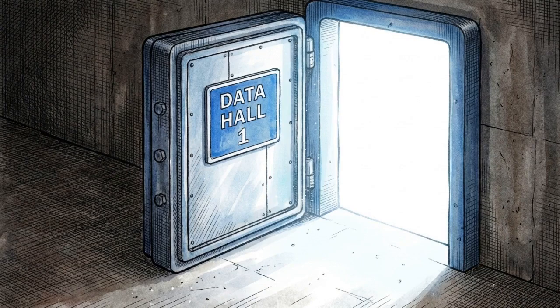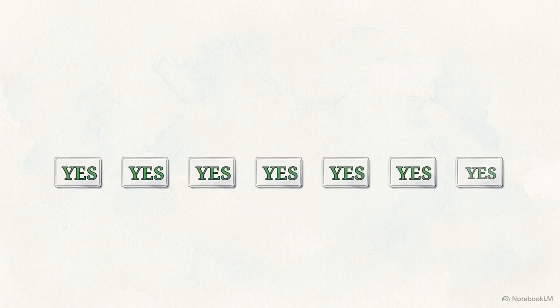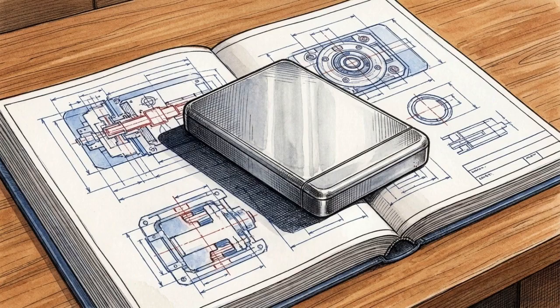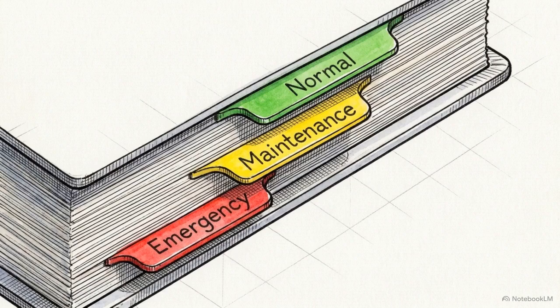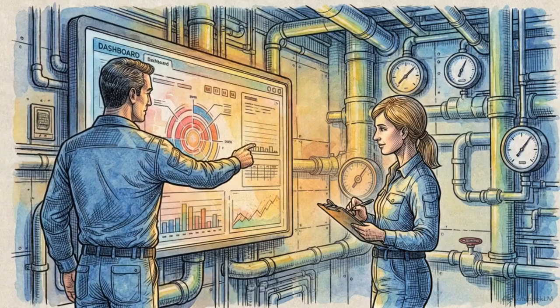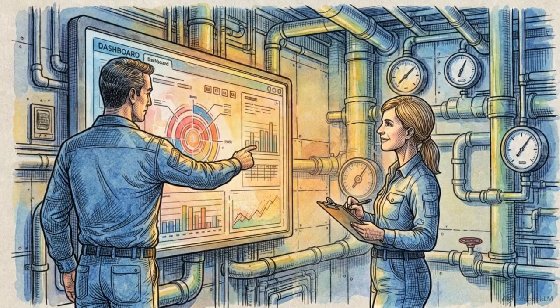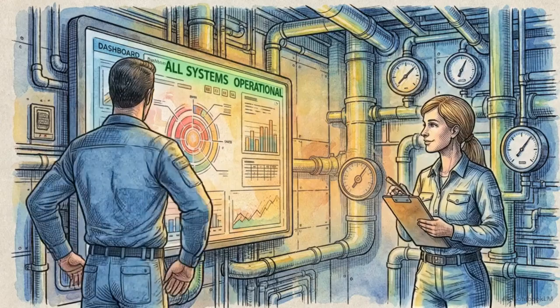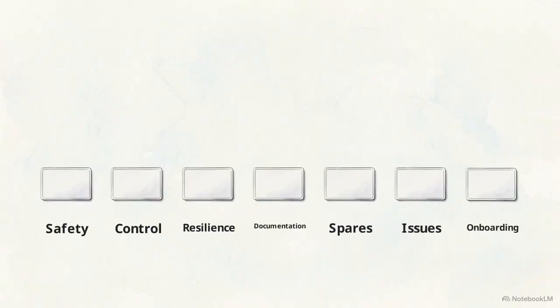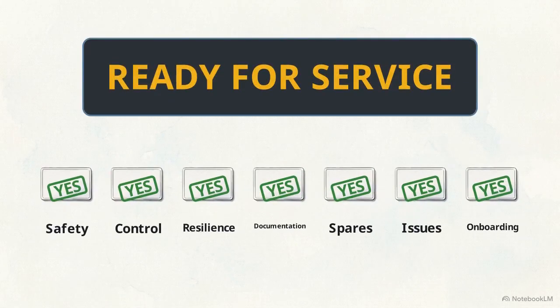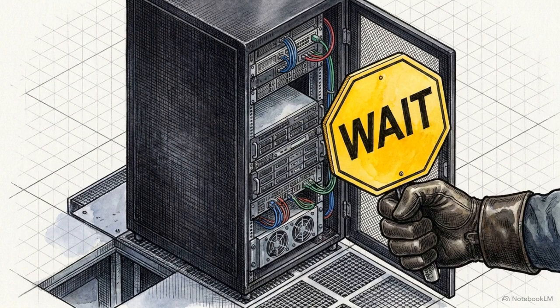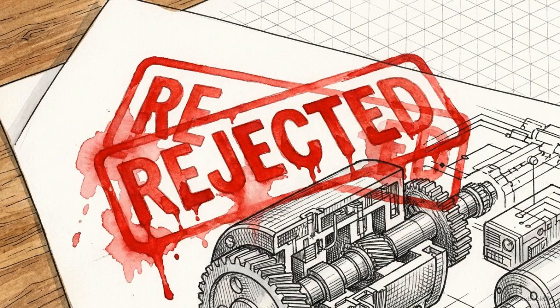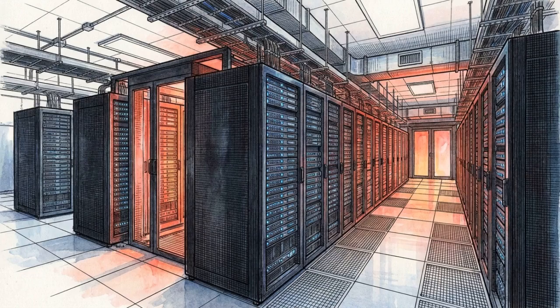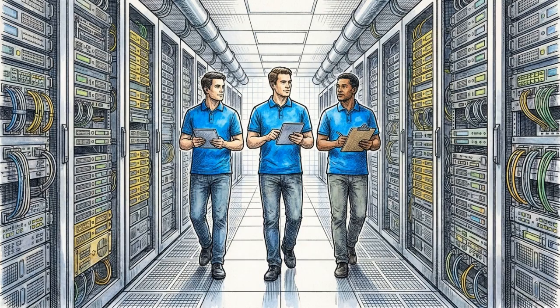Ready for service is a milestone reached only when every technical and operational prerequisite has been documented. The systems manual functions as the operating memory of the project, detailing the procedures for normal, maintenance, and emergency modes. Operator training is valid only when staff can physically demonstrate fault isolation and dashboard proficiency. Classroom attendance alone does not constitute operational readiness. The go-live decision depends on 4 factors: safety, operational control, failure tolerance, and spares availability. These must be confirmed before onboarding any IT load. No evidence, no acceptance. No prerequisite, no next gate. A data center is commissioned only when the raw evidence proves it can be operated, maintained, and recovered.